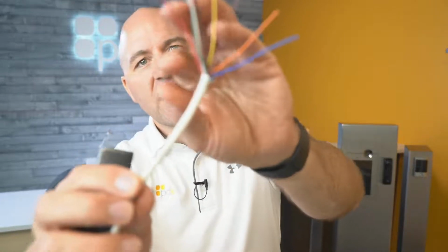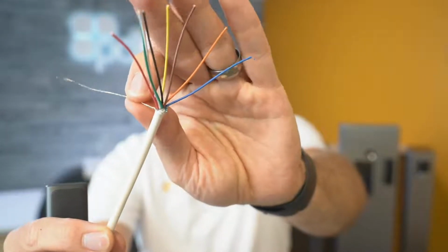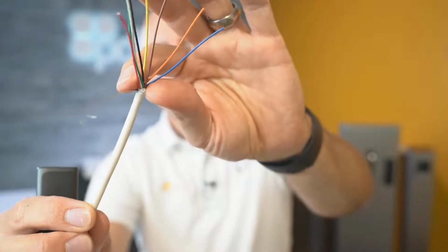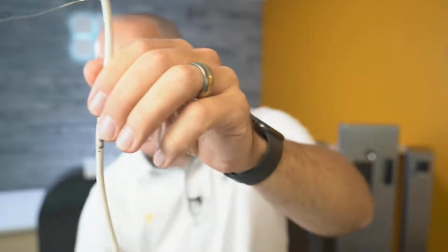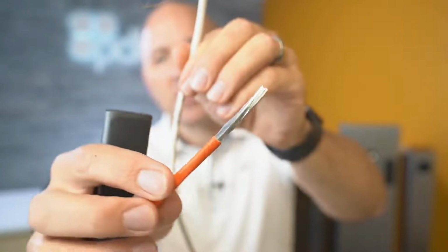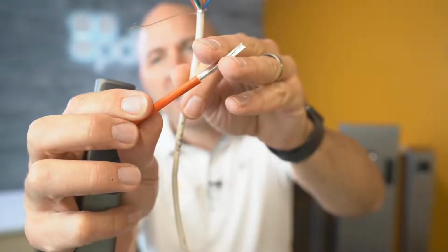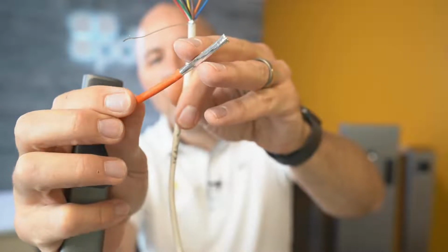Another wire coming out the side here—let me get this to focus—is just a bare metal wire. This particular reader wire is what's called a shielded wire, and you can see, since I already have it stripped out, this is the shield right here. It's almost like an aluminum or tinfoil wrapping that goes around the wire, and it protects your wire from picking up ambient noise from other power or energy sources near where your wire may be running. In most cases, every reader needs to utilize a shielded wire. It really protects you from having to go back out to an installation and wonder why a reader isn't reading correct data or isn't working correctly—a lot of times that's from ambient noise coming through the reader wire.